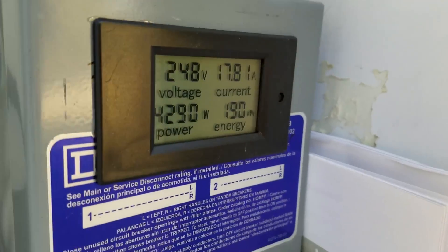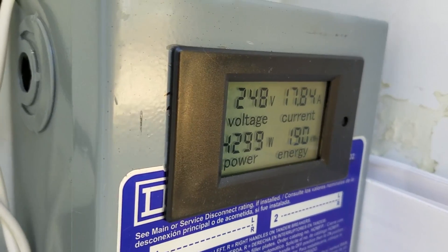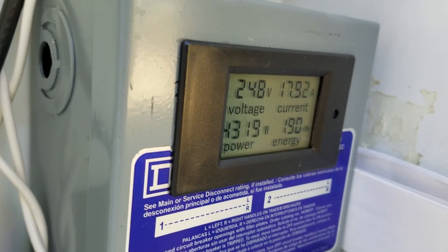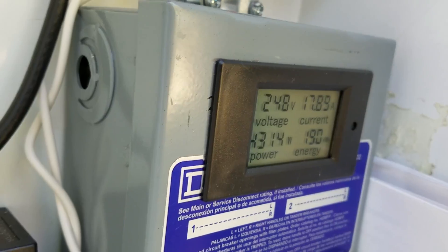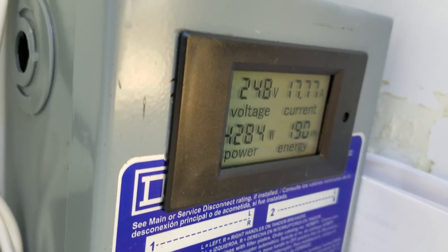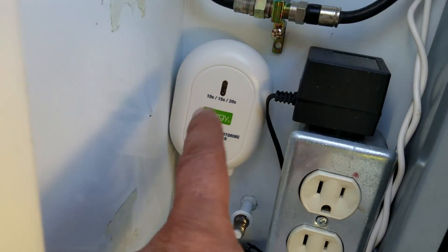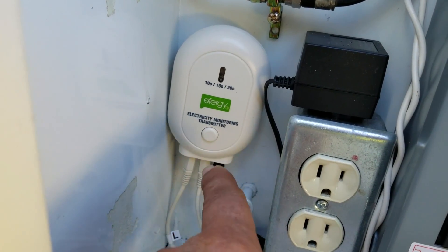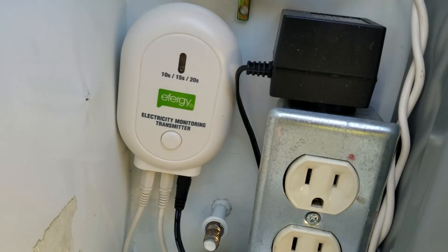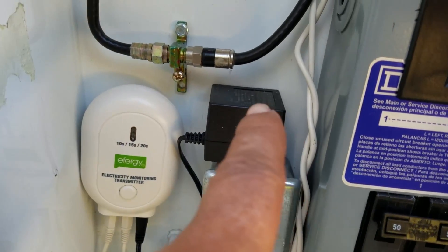Looking inside the box — if I can get rid of the reflections — the meter is showing about 4200 to 4300 watts, consistently around 4300 watts, at 17.8 to 17.9 amps shown in the upper right corner of the meter. The watts are in the lower left, and the voltage reads 248 volts in the upper left. We have the Efergy electricity monitoring transmitter here.